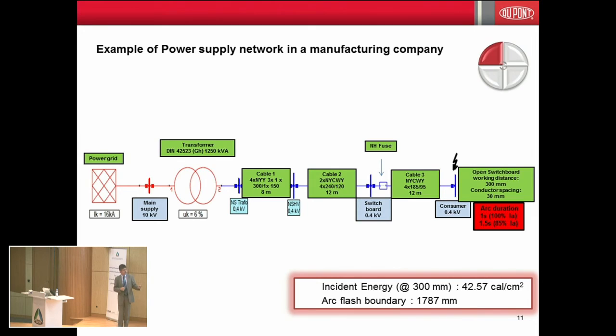In this example, the calculation came to 42, and the arc flash boundary is a little bit more than 1.7 meters. That means if you are not protected, you cannot get closer than that. So maintenance is obviously difficult since you will have to cross that line. If you cross the line, you need to be protected.